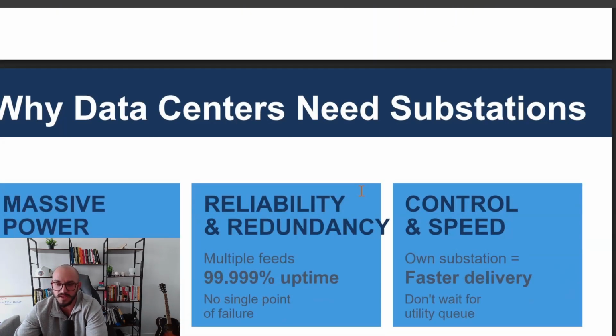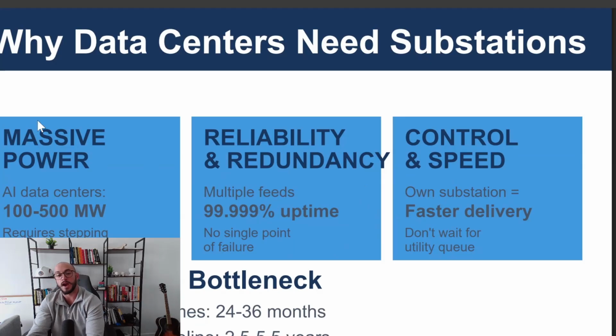Why do data centers need these substations? They need massive power. Usually that's coming from 230 to 345, or 500 kV lines - that's where the massive power is coming from and traveling in. To tap into those lines you need a substation that can step down from 115 kV plus down to actual usable voltages, because you can't just use that crazy amount of power directly.